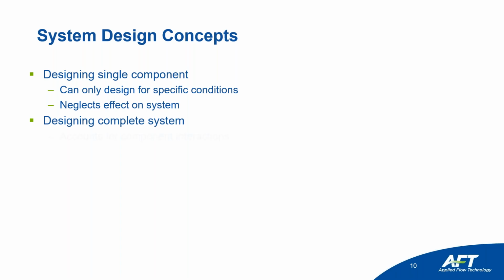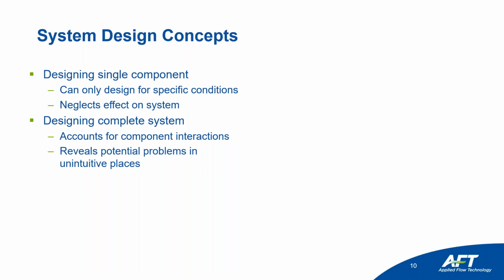The next thing is when you design a complete system and you do a good analysis and you design your system and then you run an analysis software like AFT Fathom to check and see, is your design going to work? Well, the advantage here is you can account for component interactions. When you've got pumps operating and heat exchangers having their losses being defined on resistance curves, control valves changing their operation in order to meet their set points, some funky stuff can happen, and if you do an analysis, you can see all that interacting together. This will also reveal potential problems in unintuitive places. I'm going to show you an example of that later.